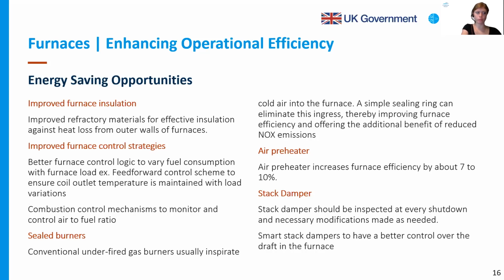Sealed burners: conventional under-fired gas burners tend to inspirate cold air. A simple sealing ring can eliminate ingress of cold air into the furnace, thereby increasing the efficiency. Also, one thing to note here is that all peepholes and header boxes must also be tightened to eliminate air ingress. That could also lead to heat loss.